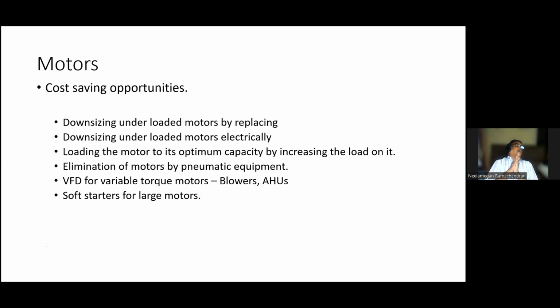having said that, I think I have another 10 minutes. I'll touch upon, not very briefly, cost saving opportunities in motors. See, everywhere now the fashion is connecting VFDs to motors. Nothing wrong. With VFD we have a technology whereby we can change the speed of the AC motor, because initially, in the 80s and early 90s, it was only DC motors where we could change the speed. Now, with the advent of the frequency drive, we use it extensively for changing the speed of AC motors, thereby getting monetary benefit.